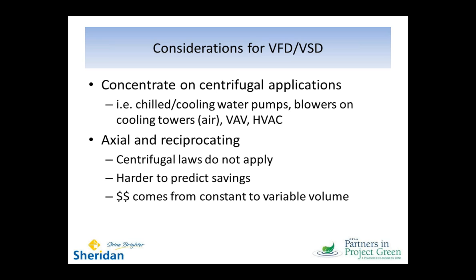When you're dealing with the axial and reciprocating loads, you really don't have the affinity laws applying. So you don't have affinity laws. It's much harder to predict your savings, but you will get some dollar savings in some cases from just reducing the amount of consumption.